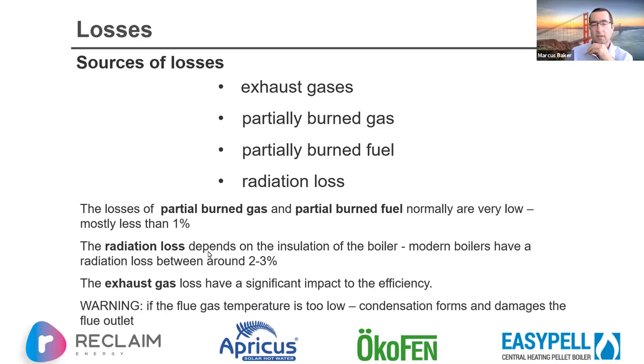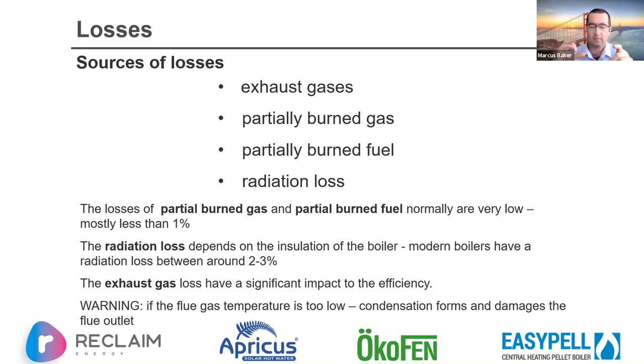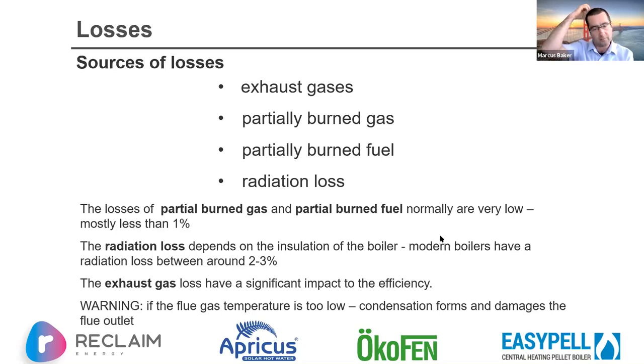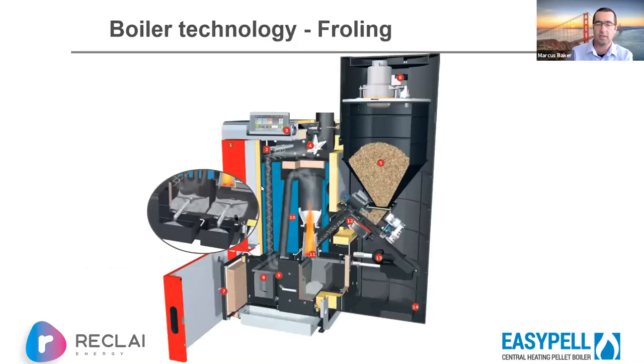Radiative losses are low because there are good levels of insulation. Anyone who's seen a pellet boiler will know the controls, display, and circuitry are all on board, and these don't like getting too hot, so the boiler must be very well insulated — otherwise it would fry its own controls. Exhaust gases can have a significant impact on efficiency, but there's a balance: if the flue gas is too cool, condensation forms and can damage the flue outlet — usually a minimum of 120 to 160 degrees.